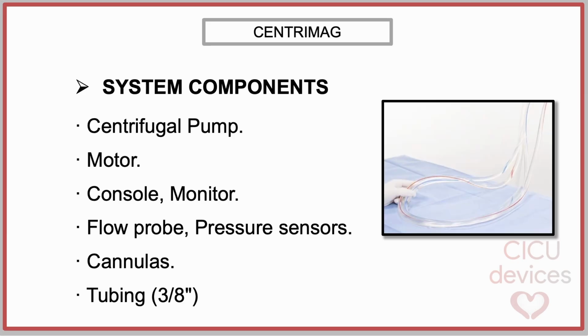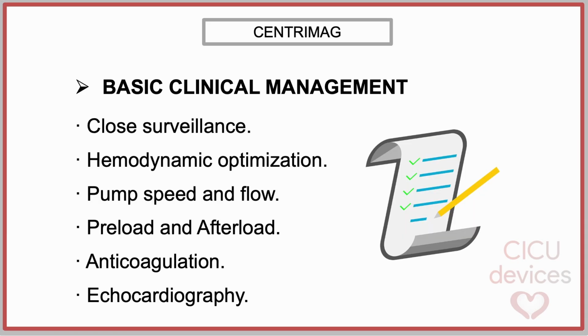system. And finally, the tubing system that connects the inflow and outflow cannulas to the centrifugal pump, forming a closed circuit for blood circulation. The tubing is designed to be biocompatible, minimizing blood activation and reducing the risk of hemolysis and thrombosis during short-term mechanical support. The CentriMag circuit uses tubing with a standard diameter of 3/8 inches. Clinical management of patients supported with the CentriMag system requires continuous monitoring of hemodynamic parameters, pump speed, and circuit flow.